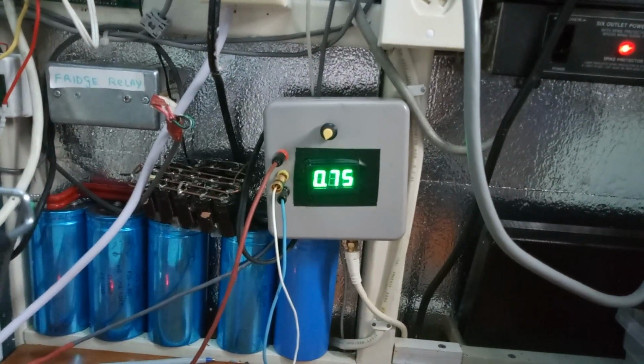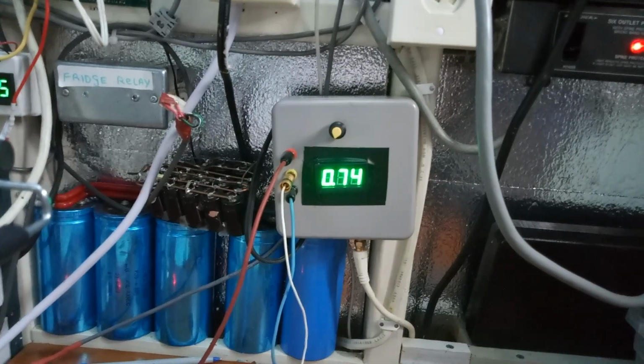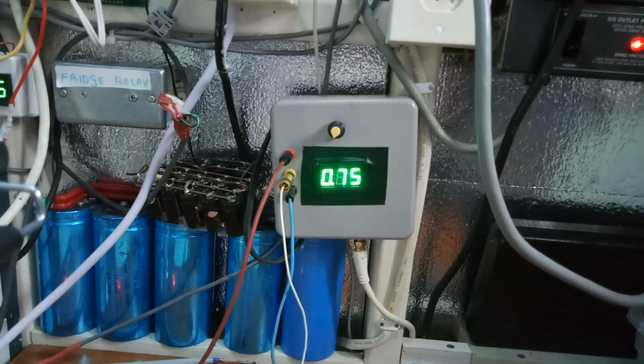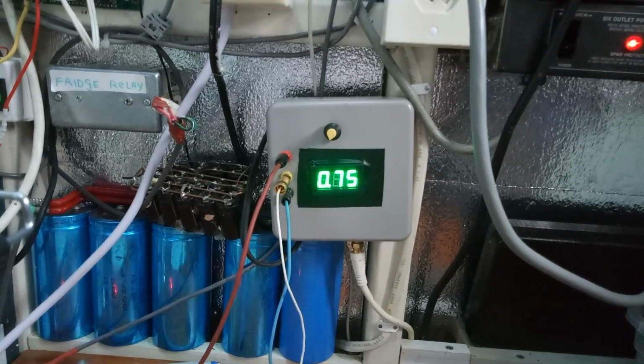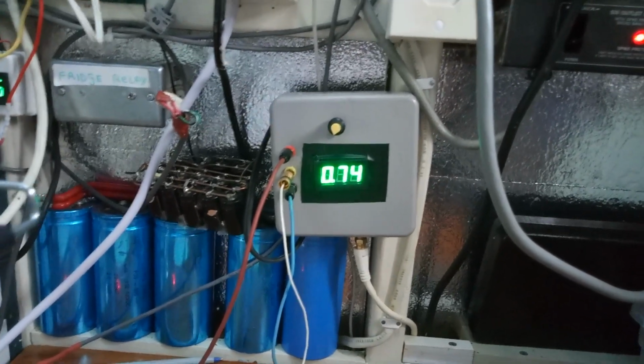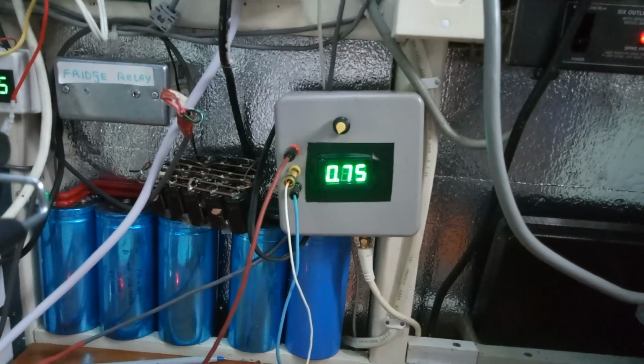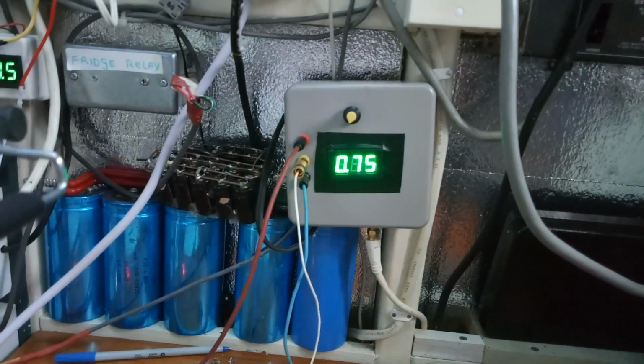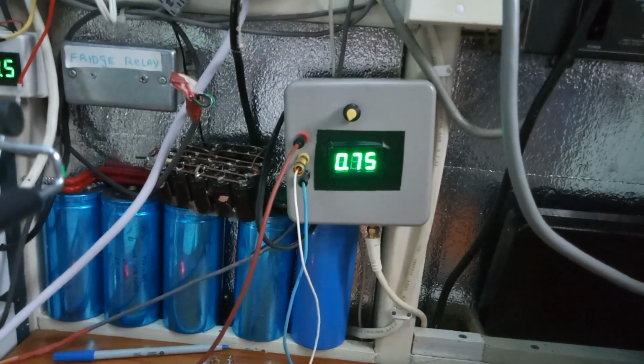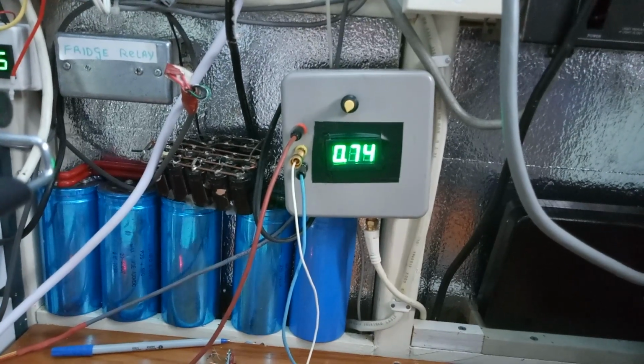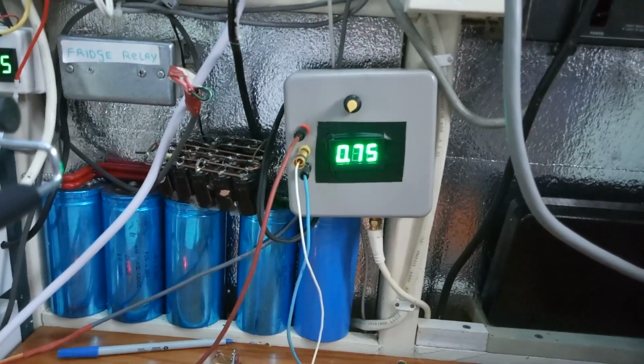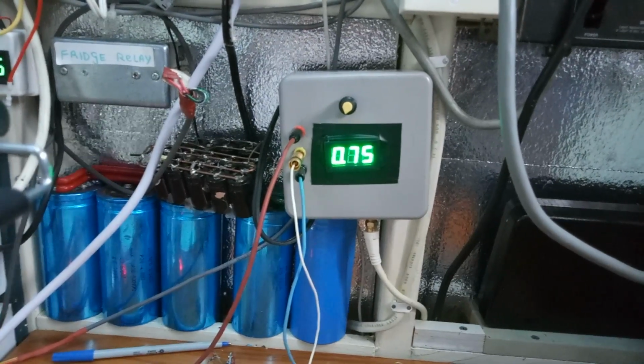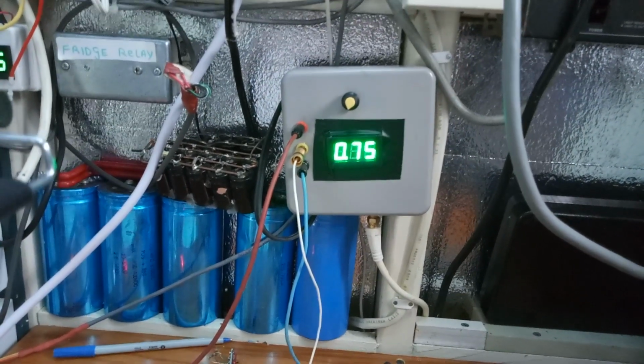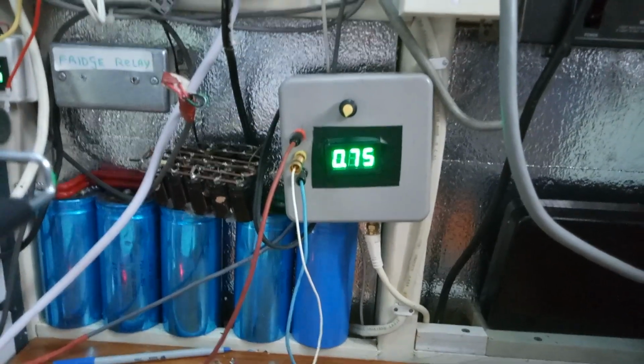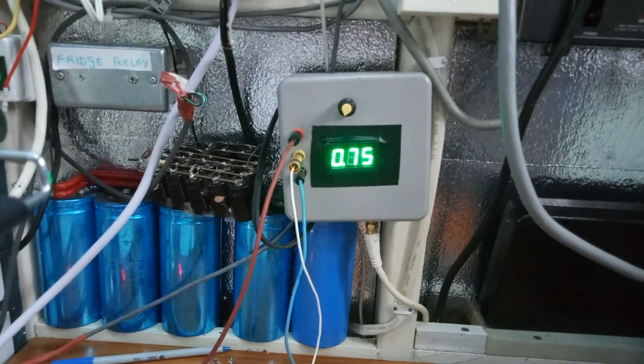This is what we call a pilot panel, and I have it set up with a load resistor on it. It's always measuring the short circuit current of the panel and producing a voltage from that. With this little adjustment up here, on a good sunny day at noon when I'm getting the maximum output, I set the output to 1 volt through a simple voltage divider. And that tells me when the panels are capable of producing 100% of the power. Any other time of the day, it'll be lower than that.